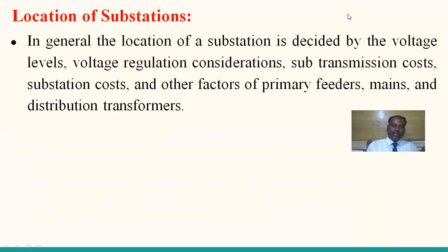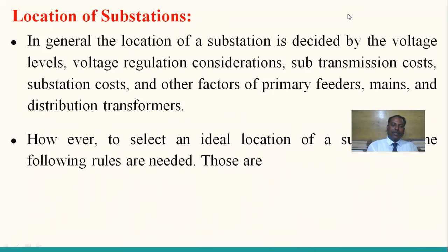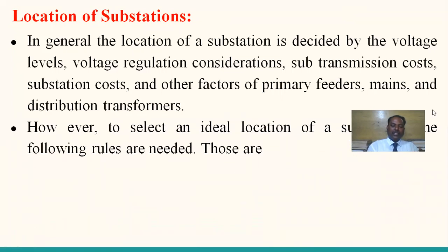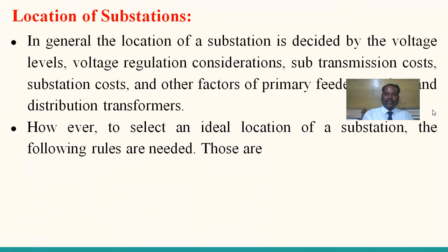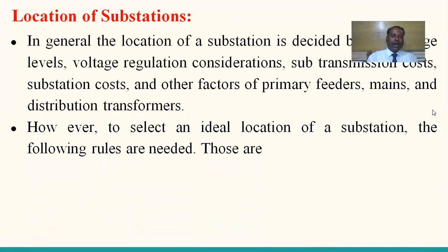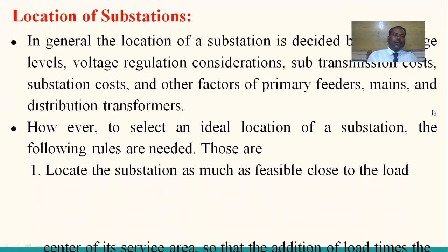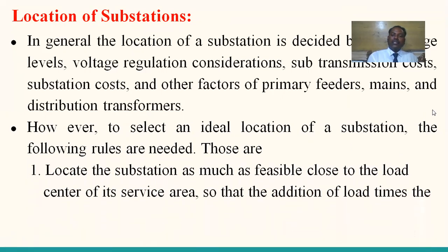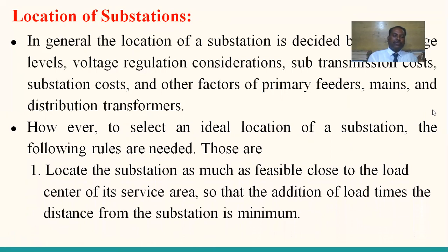So in addition to these technical parameters, there are some general parameters which are also taken into account. However, to select an ideal location of a substation, the following rules are needed. What are those rules? Rule number 1: locate the substation as close as feasible to the load center of its service area. This is a very important point from the voltage regulation consideration point of view.